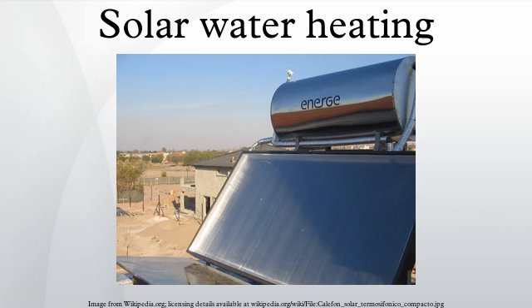Moving further north into colder, less sunny climates, the energy payback time of a solar water heating system in a UK climate is reported as only 2 years. This figure was derived from the studied solar water heating system being direct, retrofitted to an existing water store, PV pumped, freeze-tolerant and of 2.8 square metre aperture. For comparison, a solar electric installation took around 5 years to reach energy payback, according to the same comparative study.